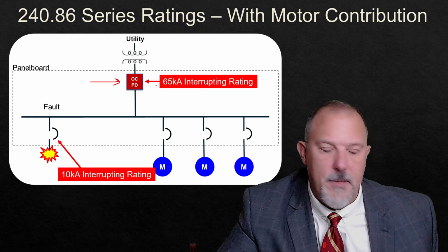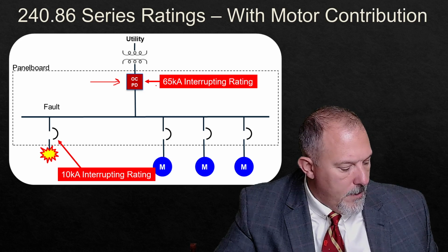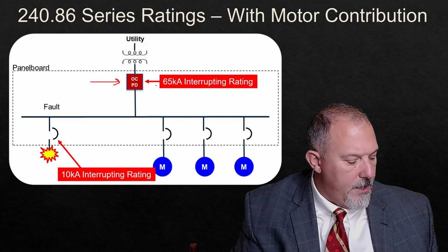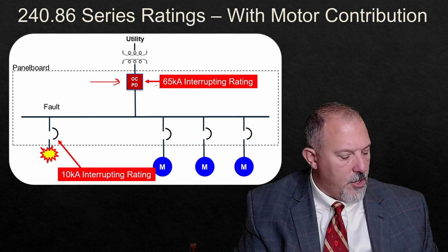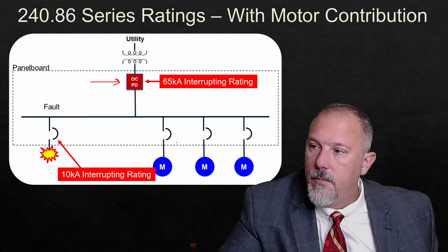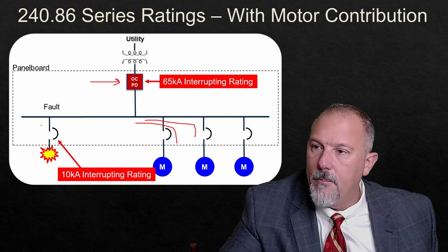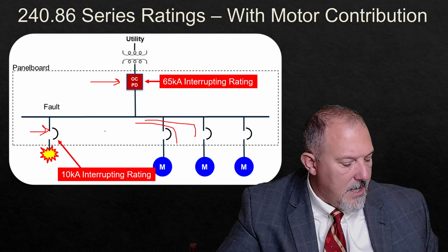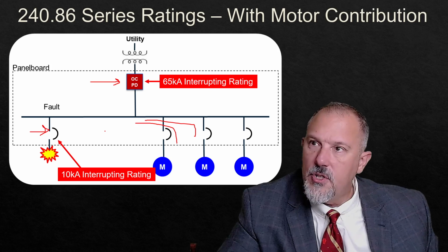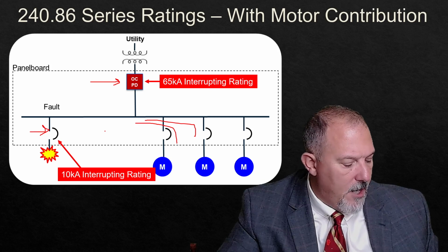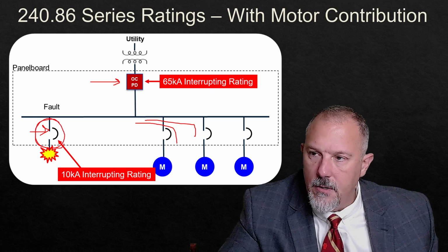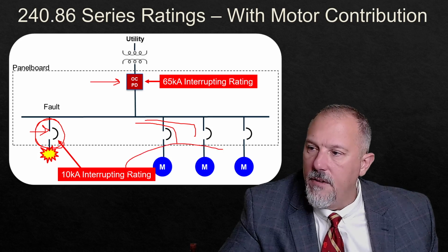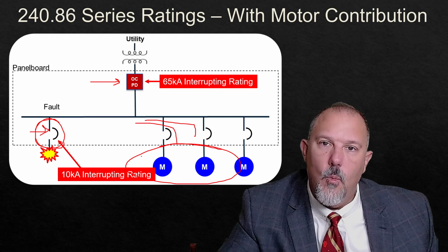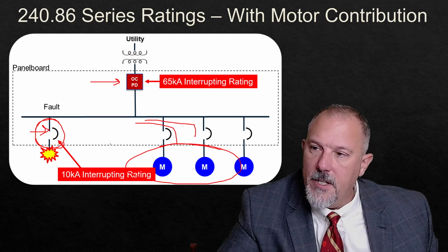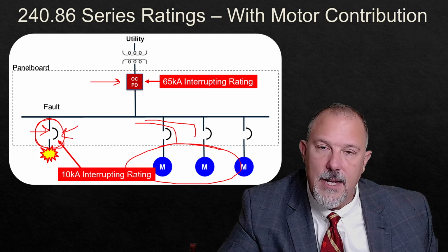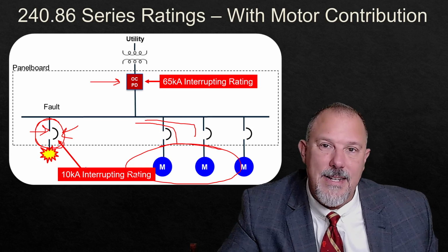This would be my 65K interrupting rating of a series-rated combination. And on the lower-rated circuit breaker. So in between those two, my motor contribution is coming in between that breaker and that breaker. It says the sum of the motor full load currents exceeds 1% of the interrupting rating of the lower rated circuit breaker. So if this is a 10K breaker, my motor full load amps, and I add all of these up, I cannot exceed 1% of the interrupting rating of that overcurrent protective device. So if it's 10,000 amps, 1%, 100 amps. I can't have full load amps exceed 100 amps.